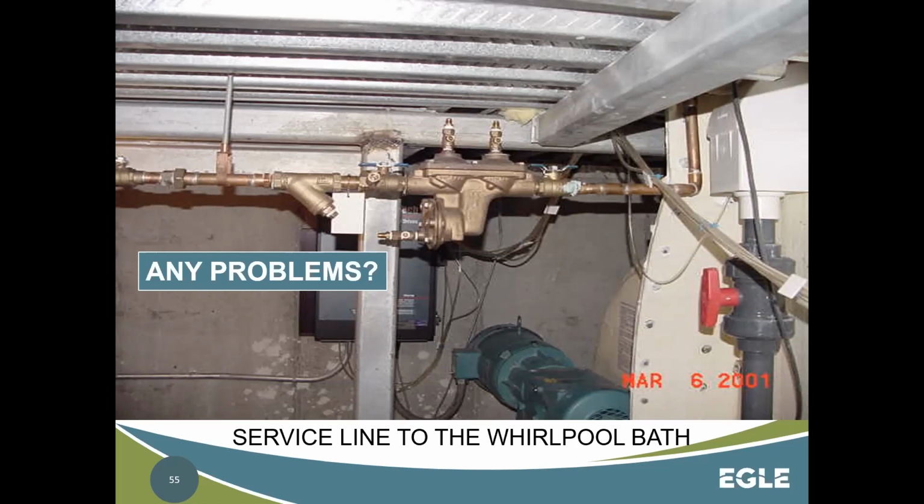isolated. In this case, they had a whirlpool bath that was used as some of the therapy, and they had an RPZ that was put in place here, which was the correctly chosen way to try to protect against that use.